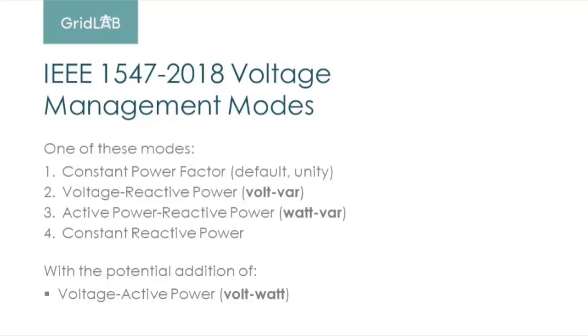So you get to choose one of these 4 modes. You can't run multiple modes, but you can also add on volt-watt. These 4 modes are constant power factor, which is the default mode set to unity, so you can set the device to run at like 0.95 leading or 0.95 lagging. You have volt-var, which I'll talk a little bit more about. That's voltage-reactive power. You have active power-reactive power, or watt-var, and constant reactive power.